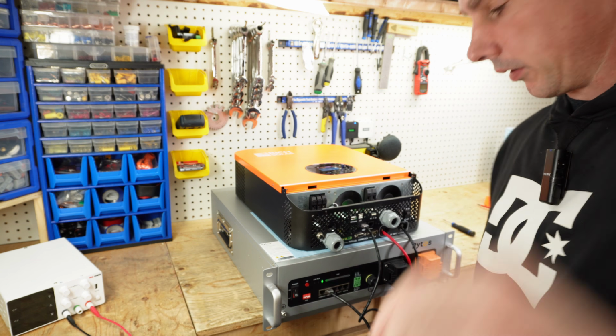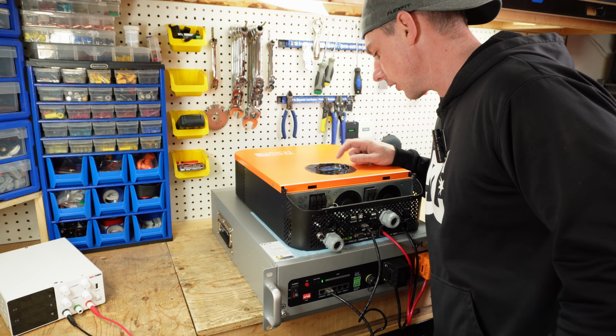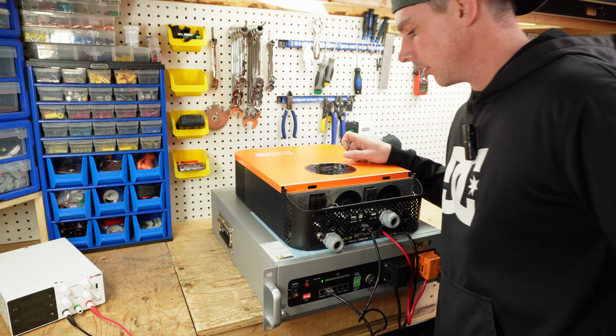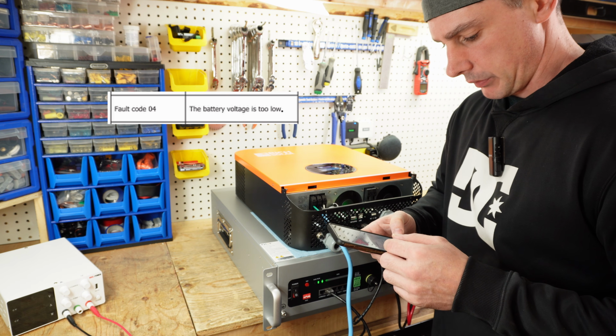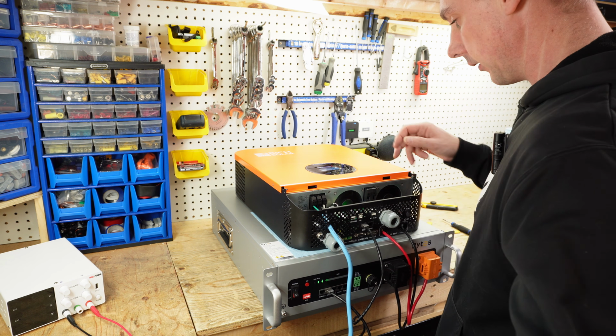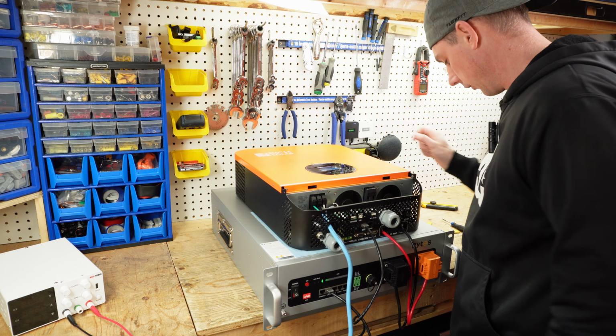So give me a minute. Now I'm going to hook up utility power to encourage charging to see if we can't get that fault to go away. Fault code 04 is battery too low. So the battery is actually giving a low voltage warning, which is great.